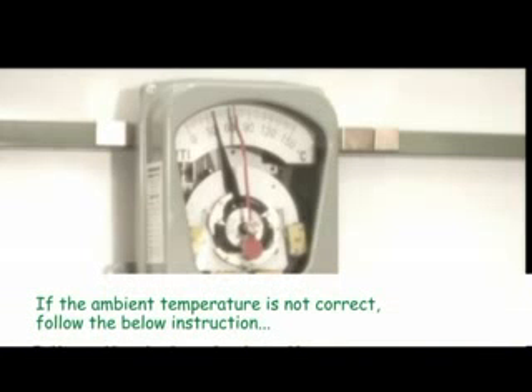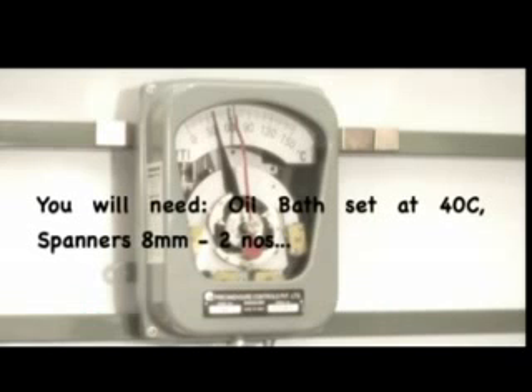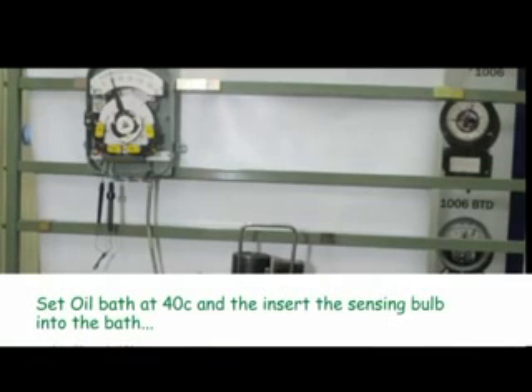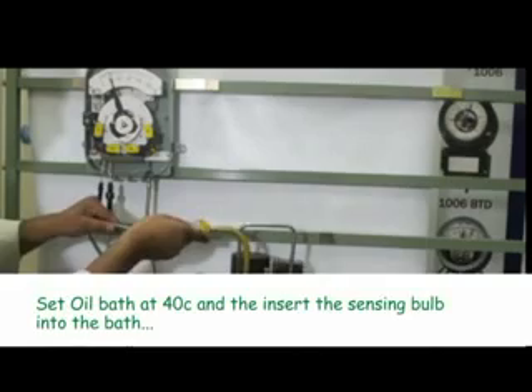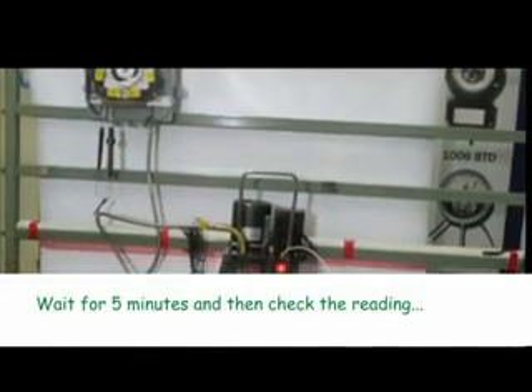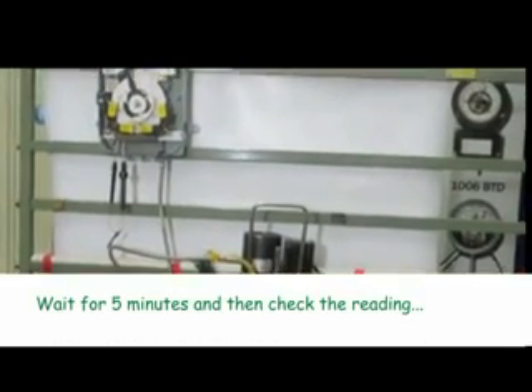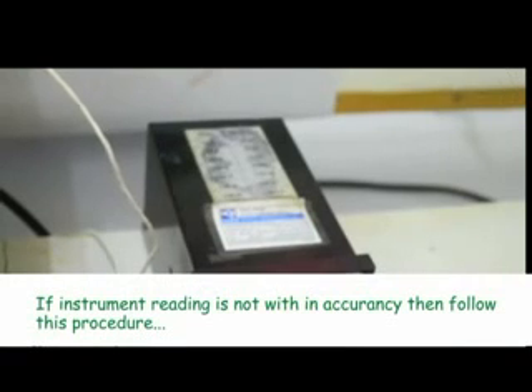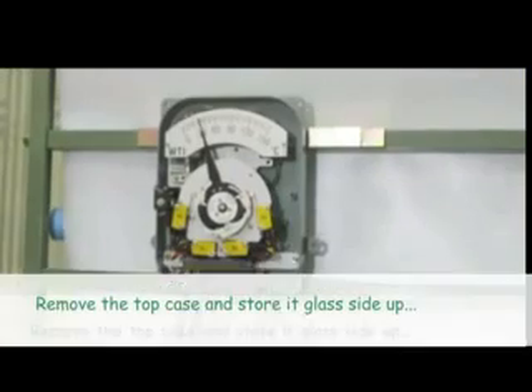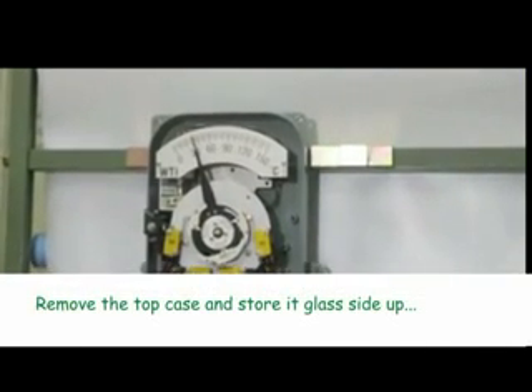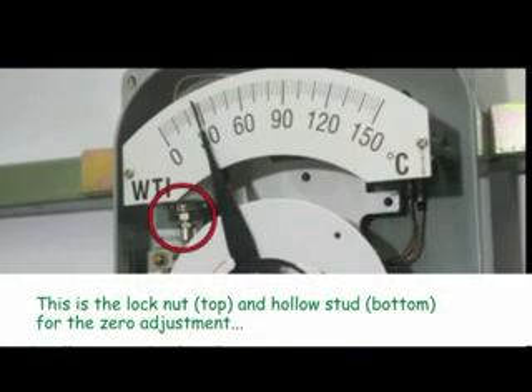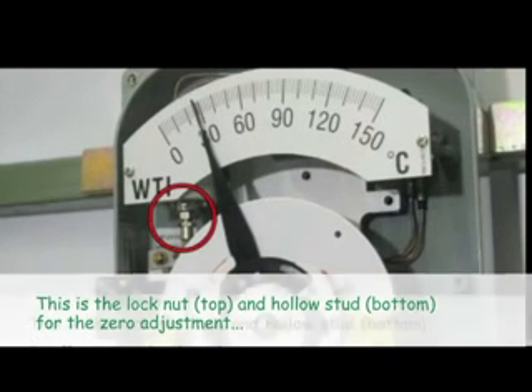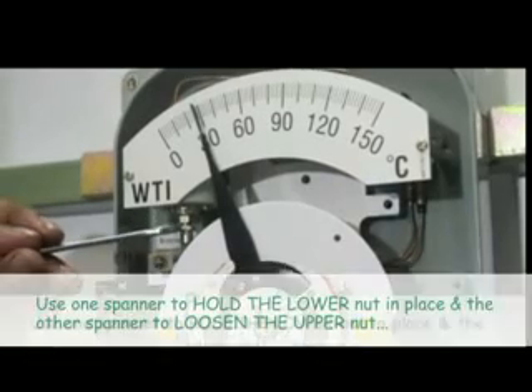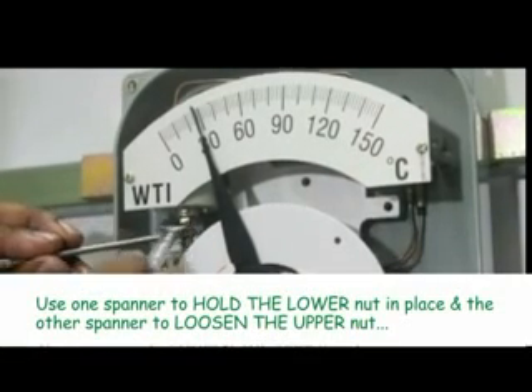Minimum adjustment procedure. If the ambient temperature is not correct, follow the below instruction. Set the oil bath at 40 degrees centigrade and insert the sensing bulb into the bath. Wait for 5 minutes and then check the reading. If the instrument reading is not within accuracy, then follow this procedure. Remove the top case and store it glass side up. This is the lock nut on top and hollow stud at the bottom for the zero adjustment. Use one spanner to hold the lower nut and the other spanner to loosen the upper nut.